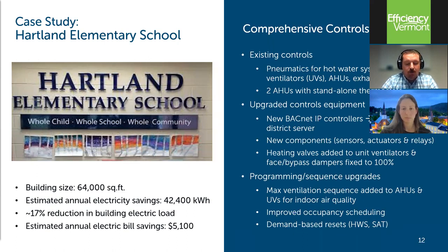We were able to go directly to the server with the new controllers. All the pneumatic components were replaced, so sensors, actuators, brand new valves, for all the equipment. For the 2 air handling units that had standalone thermostats, we reused some of the actuators and relays, but added new sensors. We also had some unit ventilators with face/bypass dampers.